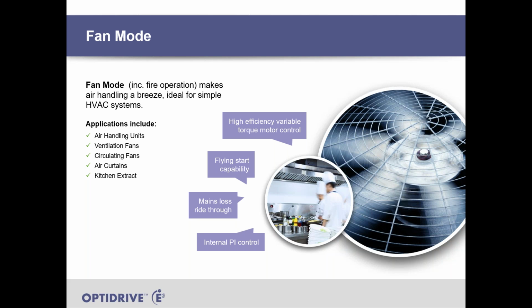We've also got very good mains loss ride through. So if you get a dip in the mains, then the drive remains powered because the fan will actually turn into a generator and push power back into the drive. So that helps to keep the drive powered up in short-term mains loss type situations. We've also got fire mode in the drive as well. We can use it for smoke extraction type applications, so that if the drive gets a signal to say that it needs to be in fire mode, then it just ignores non-critical trips and will just keep on running as long as it can.